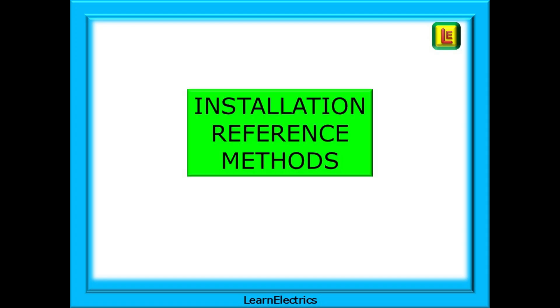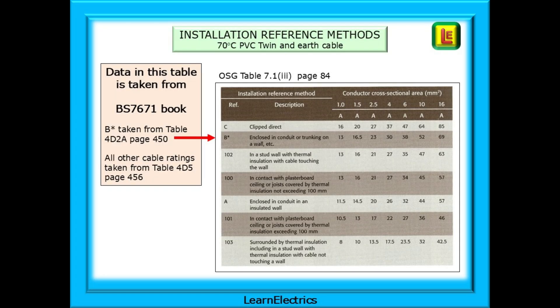What are the different installation reference methods? Page 84 of the On-Site Guide shows Table 7.1.3 for PVC twin and earth cable. It shows the reference methods down the left side and the maximum amps for different cable sizes along the top. Taking 2.5 square millimetre as an example, using reference method C - clipped direct - the cable will take up to 27 amps. But the same cable for method 103, completely surrounded by thermal insulation, the maximum is just 13.5 amps - half the previous method. This data comes from the brown BS 7671 wiring regs book.